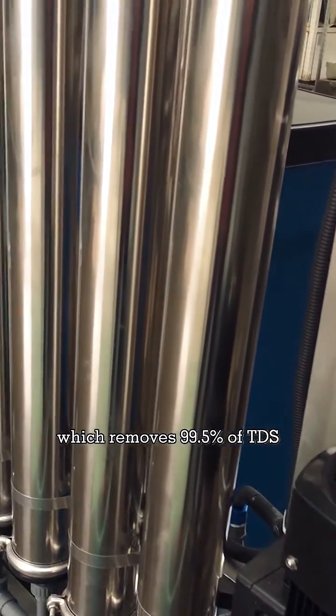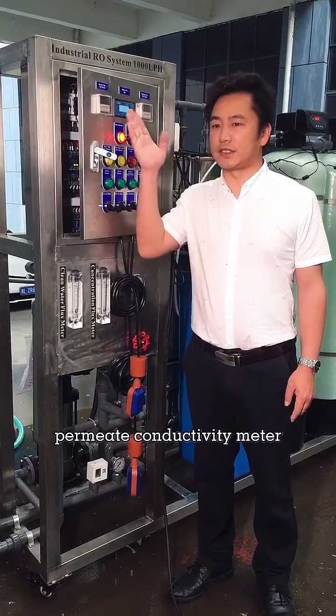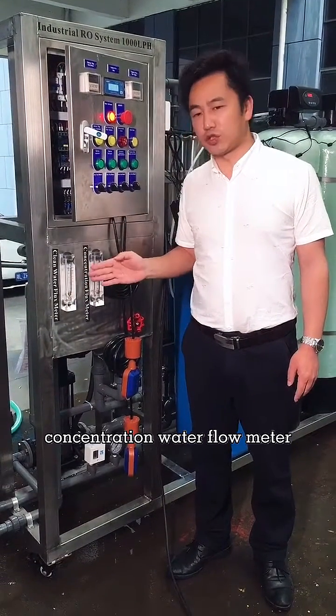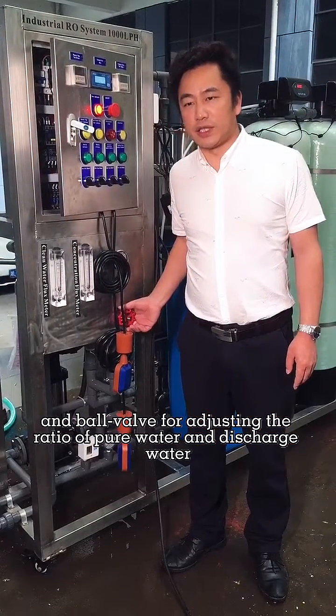The membrane removes 99.5% of TDS. This automatic control panel includes a permeate conductivity meter, pure water flow meter, concentration water flow meter, and a ball-valve for adjusting the ratio of pure water and discharging water.